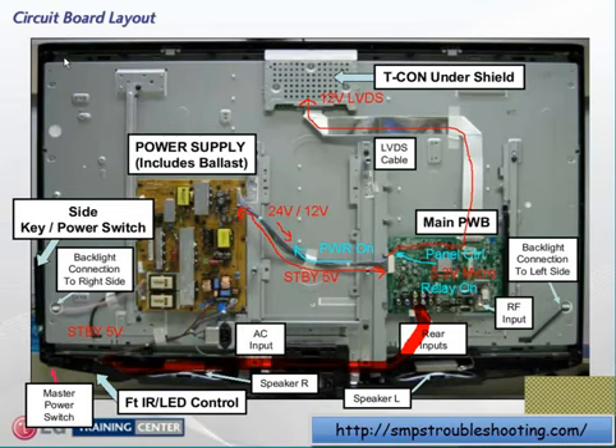Back up one step before that panel control command. Remember when power on arrived at the power supply, it kicked off the 12 and the 24 volts. It also turns on a secondary voltage side over here, that if you were reading that fuse, you would see it nearly triple in voltage. But what it does is a 105 volt DC supply is generated, which actually drives those FETs that fire up the transformers. But the transformer at this time is not being driven.